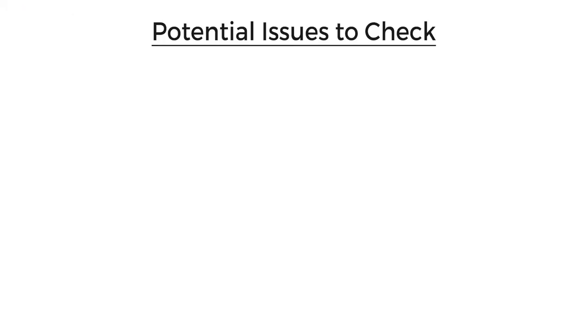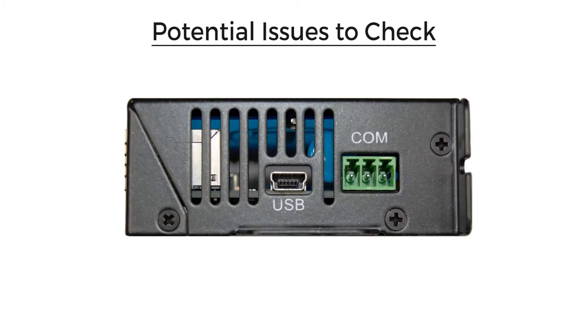Now if the communication is not working, the following are the potential issues to check. First, check the 485 connections.